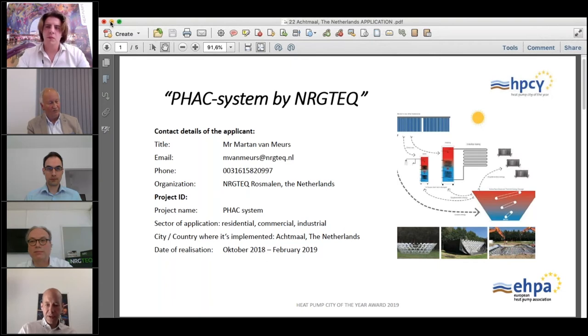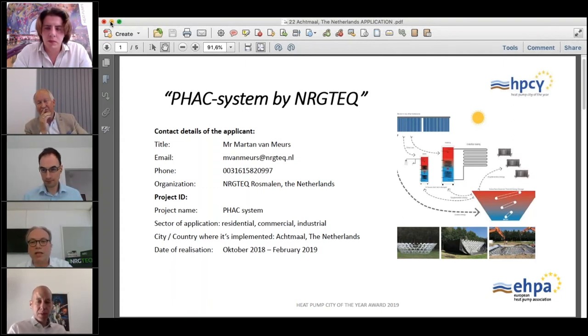And then the heat pump kicks in after that. So the system itself provides 100% of the heat. Yeah. When we start on the heating season, we run on the energy or heat produced by the system itself at the same moment. In midwinter, there's not much solar energy, so the storage will be asked to provide all the heating. And at the end of the heating season, as you mentioned, Thomas, if there is still a heating demand, we can change flow directions and start a heat pump if necessary. But we try to have a passive heating system and not run the heat pump for heating purposes. Okay. Yeah, but you run it for cooling, so that's likewise fine. Do it with electricity produced at the same moment.